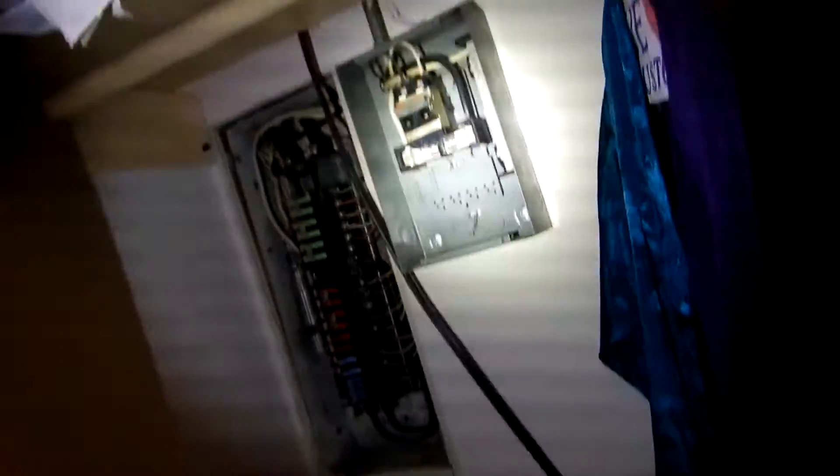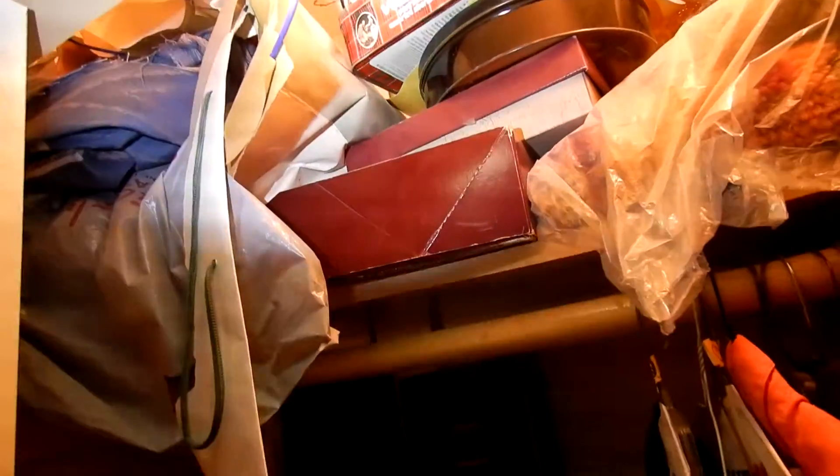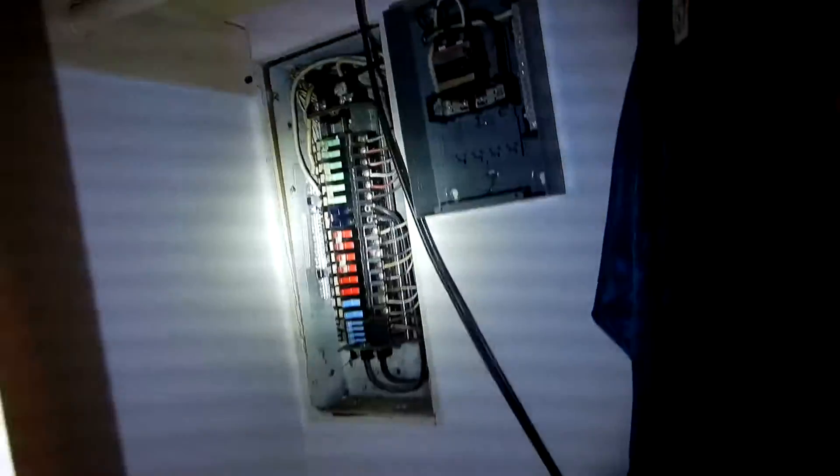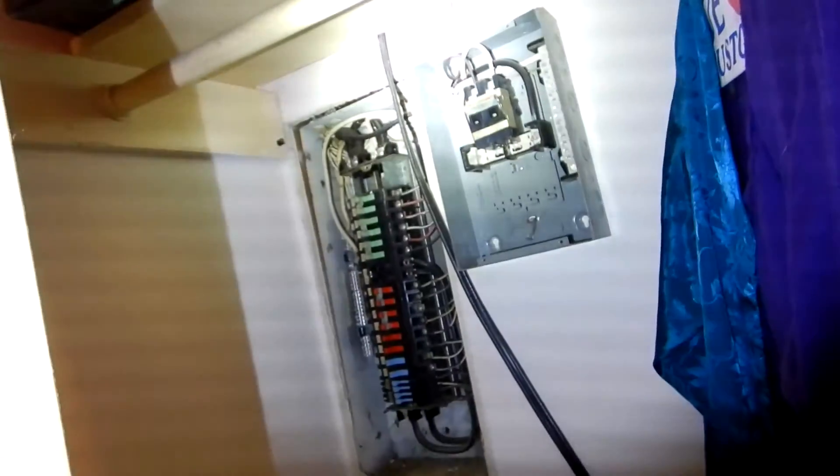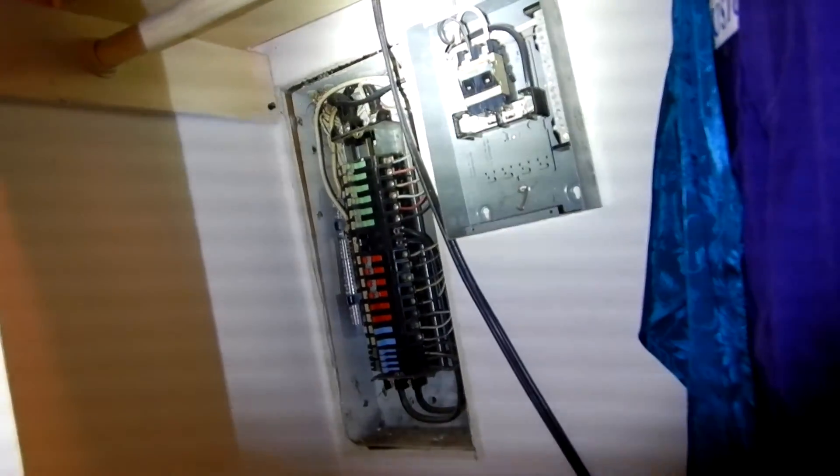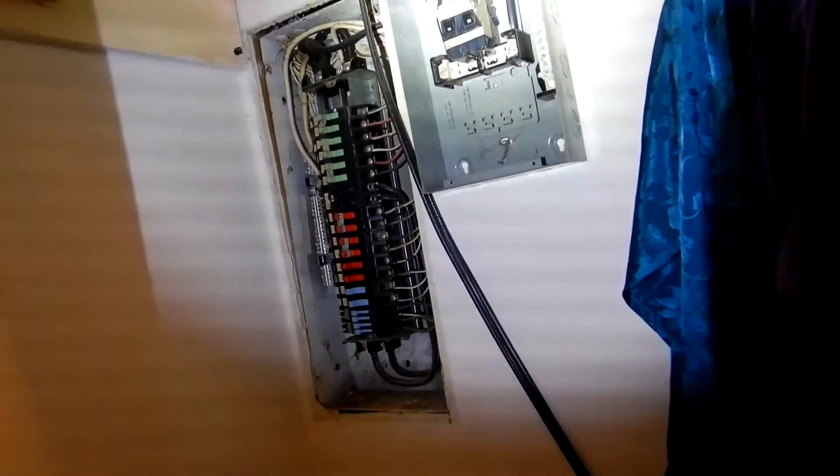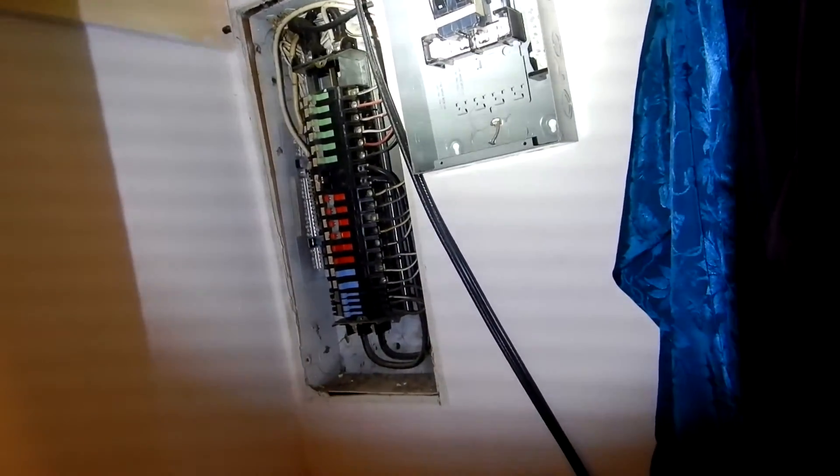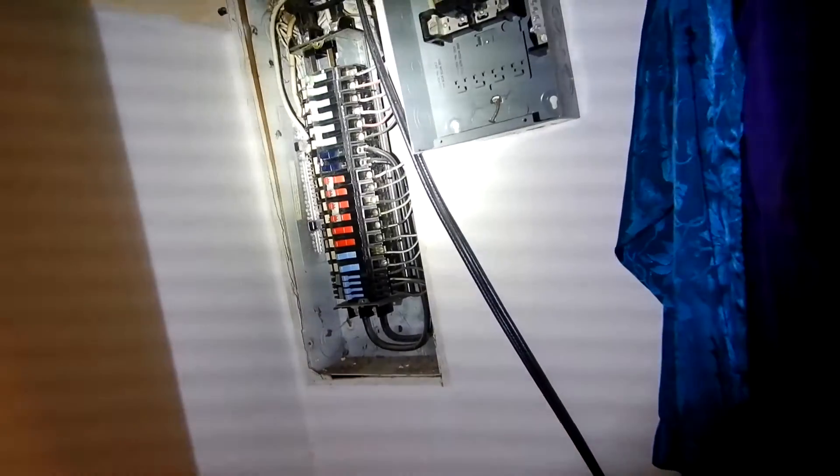Bonding locations not labeled, although we do know it's on the water heater and that conduit goes up into the attic space. I'm gonna go outside and see if I can get a clue because I'm thinking that goes to the condensing unit.